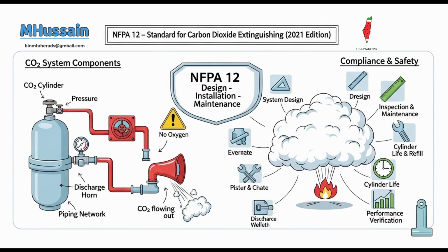Yes, the quantity requirements are different. For CO2 quantity requirements in local application systems, the amount is based on the total discharge rate needed to blanket the hazard area or volume and the specific time required for extinguishment. Rate and time. When high-pressure storage is used, that is, cylinders at ambient temperature, the computed CO2 quantity must be increased by 40% to determine the nominal cylinder storage capacity. 40% extra for high pressure.